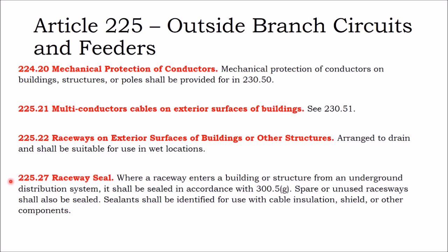And so I've made this mistake before. We had an underground service entrance conductor coming up from the utility and then going back down into the ground. We had the underground service connection coming in from the utility, and then we had power going into the home, and then we did a line side tap to stay outside this guy's log cabin.